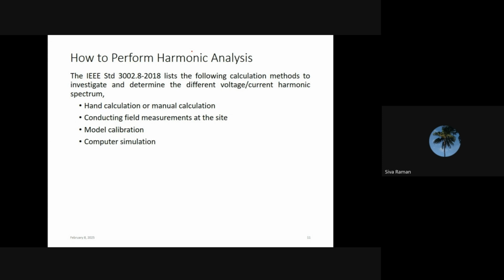Okay, so continuing further, from here onwards I will explain how to perform the harmonic analysis, what data are required, and what methods are available for harmonic analysis. For your information, IEEE standard 3002.8 was published in the year 2018. This standard is for commercial and industrial power plant harmonic analysis, but the information provided in this standard is applicable to all types of harmonic analysis. Based on this standard, we can perform the harmonic analysis in 4 ways.